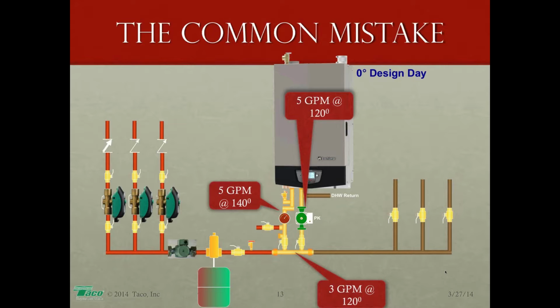The lower the return water temperature, the more that boiler is going to condense. I think you start condensing at about 128 degrees return water at sea level. If I'm wrong on that, someone chime in. But I believe it's 128 degree return water temperature at sea level. That's when you start the condensing process. And the lower the return water temperature, the more that sucker's going to condense. All right, and the more you want it to condense. Okay.